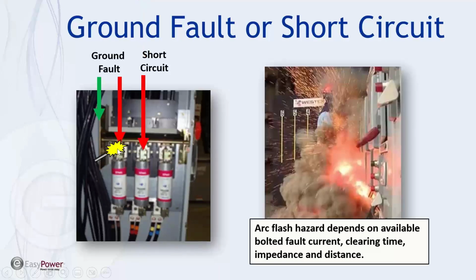If you've got a short circuit, it's going to be the same thing. You'll have something across it, and it's going to cause a flash. And very often, if it's 480 or higher, it'll ionize the air, and then it'll create this plasma and turn into a three-phase fault, and then you have a real big mess on your hands. So we're going to talk about what causes these things and what we need to do to prevent them.